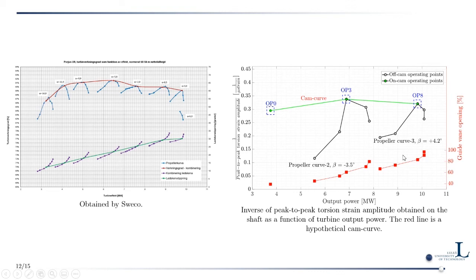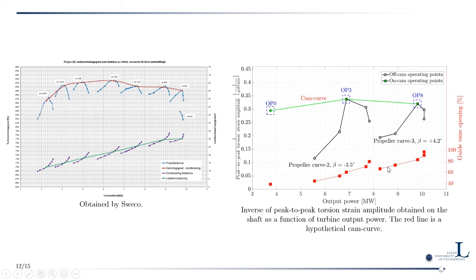Besides the strain correlation, torsion measurements on the shaft showed potential as a good candidate for index testing on Kaplan turbines. The inverse of peak-to-peak torsion strain amplitude (Y-axis) versus output power (X-axis) shows local maxima for each propeller curve corresponding to the best efficiency point, with red guidelines indicating the trend. This result suggests that torsion shaft measurements could be used to update the index test chart for Kaplan turbines.